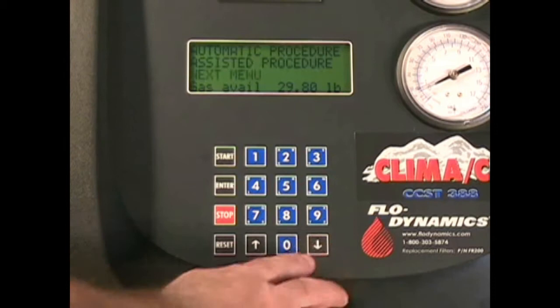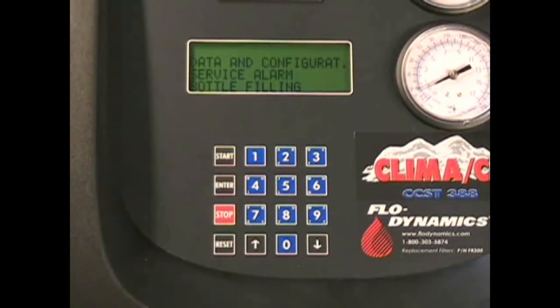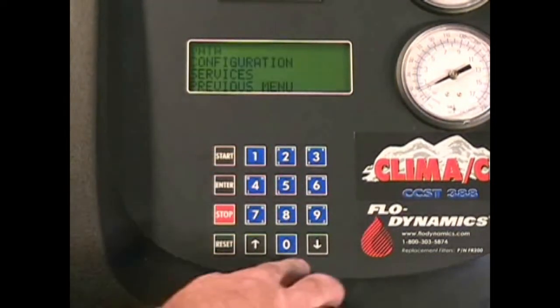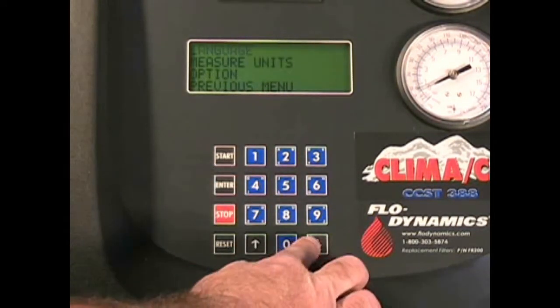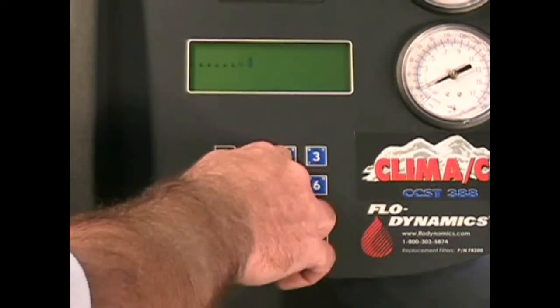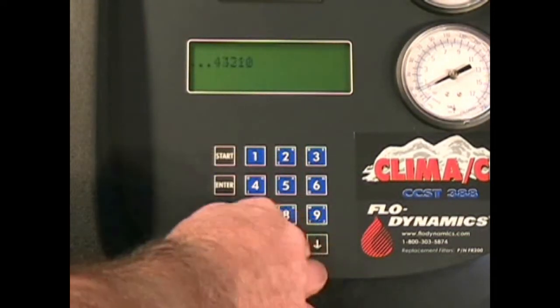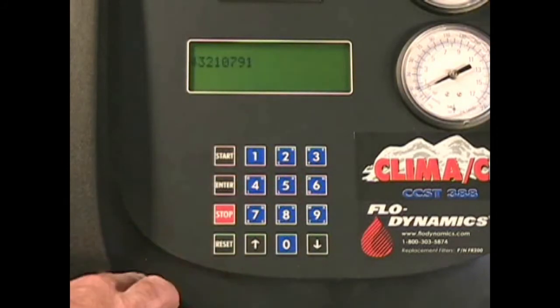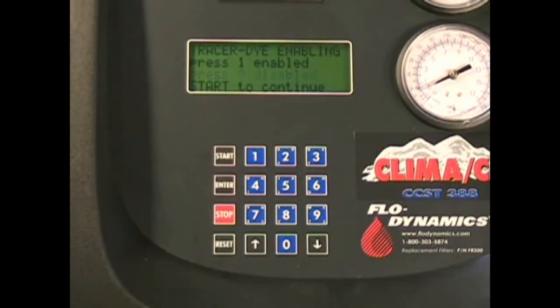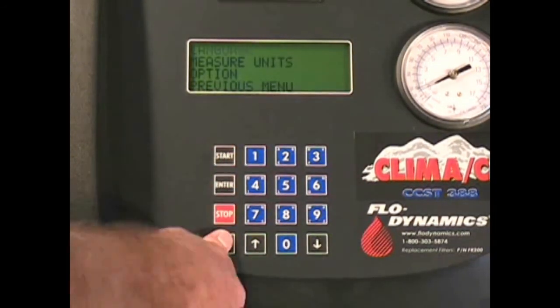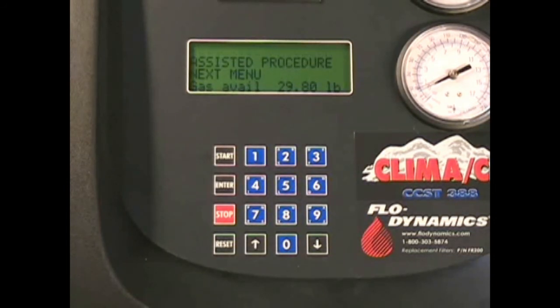Turn the unit on, go to Next menu, Data and Configuration, Configuration, then Options. Type 43210. Then press 1 to enable dye injection. Press Start to continue. It is recommended that the oil scale be recalibrated after adding the DK300. Calibration procedures can be found in your manual.